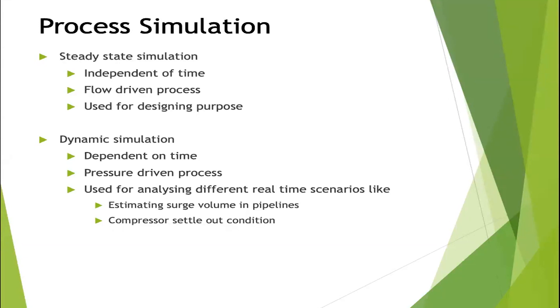Dynamic simulation is time-dependent. Once a parameter is changed, it shows you the sequence of changes that will occur in the plant. These are pressure-driven processes — changing the pressure affects flow rates and downstream equipment behavior. Dynamic simulations are used for estimating surge volumes in pipelines, determining compressor settle out conditions, and developing operator training simulators.